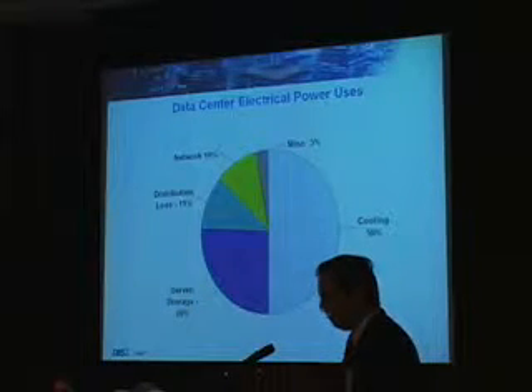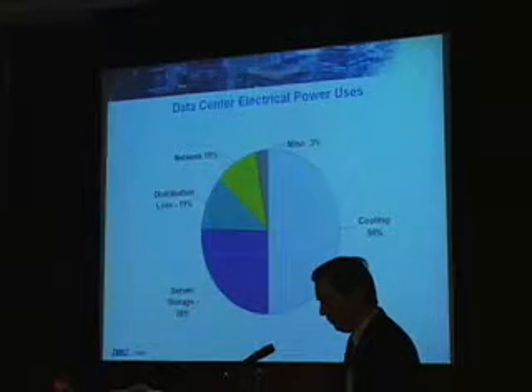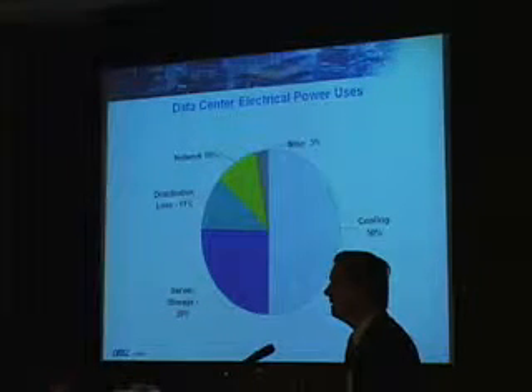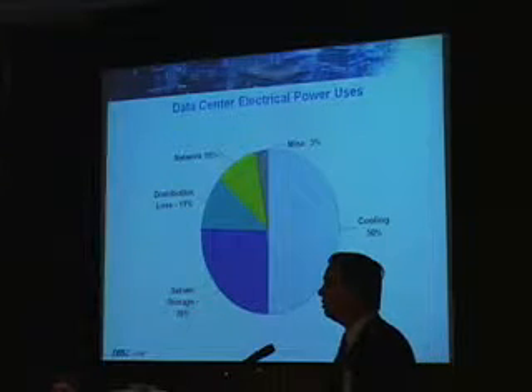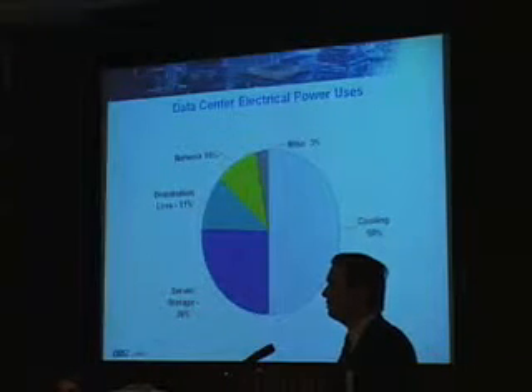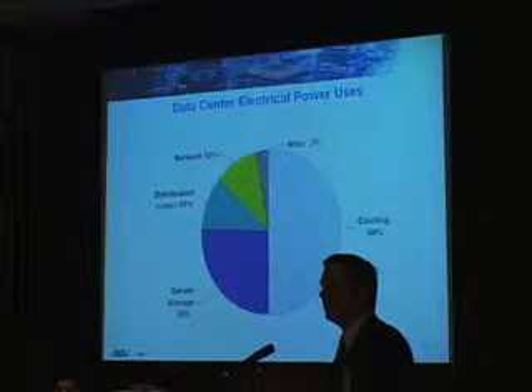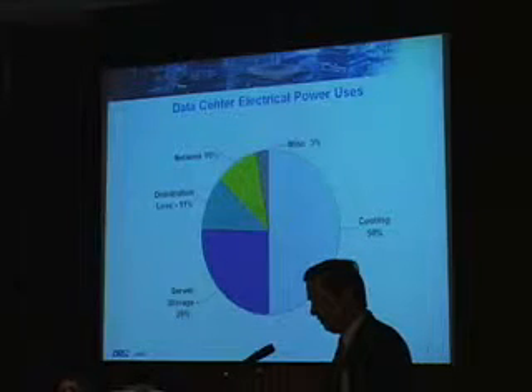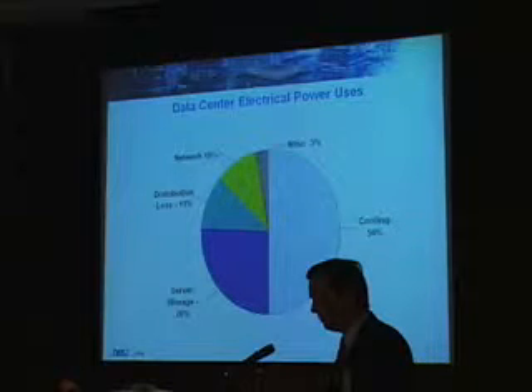Data center electrical power use: if we look at the data center, your servers and your storage are using about 26% of the power. When we talk to a lot of businesses, we ask them how much power they're using. They go to their UPS and tell us they're using 100 kW, but that 100 kW is only about 25% of the power you're actually using. There's an additional cooling load for cooling, additional load for distribution, network, and just miscellaneous.